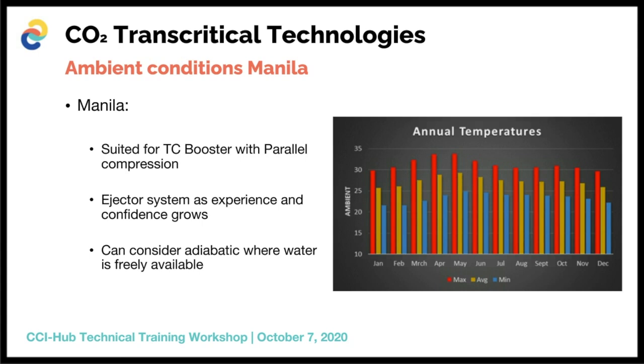But the main outcome of what I can see when looking at the ambient conditions that you will find in the Philippine regions, from looking at the technologies before, is that a CO2 transcritical booster system fitted with parallel compression would be a very suitable solution for the Philippine market, as the average temperature is well below 30 degrees Celsius year on year, and even your worst case high ambient conditions of up to 34 are still below 35 degrees Celsius, where your parallel compression systems still make you more energy efficient up to 37 degrees Celsius ambient.